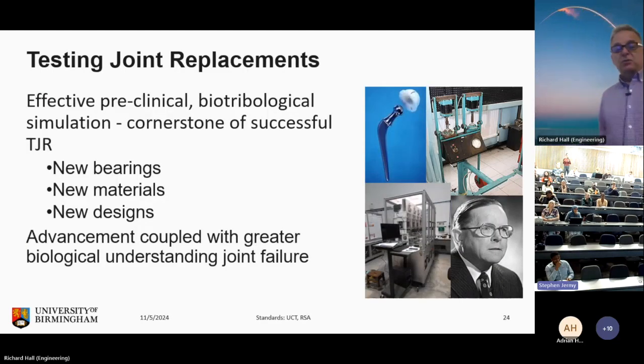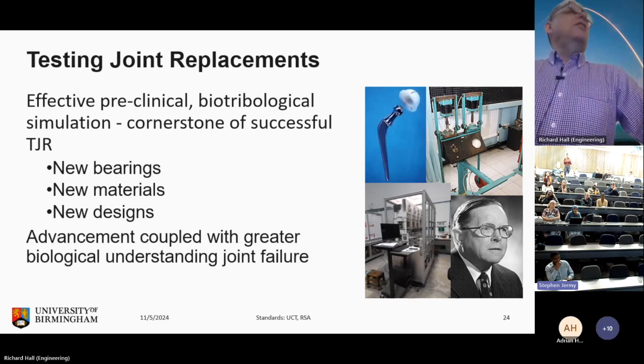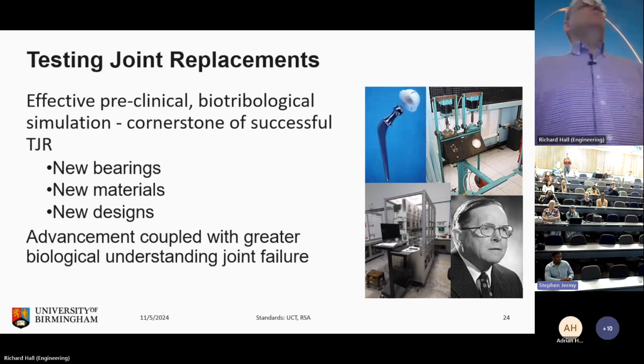So we test joint replacements. You come to our laboratory, we have big machines ranging anywhere from £250,000 to £1.5 million, £2 million, depending on the sophistication, the size, and the level of control that these machines exhibit. They can weigh anything from a few pounds to several tons, which has caused Birmingham a bit of an issue when trying to put these heavy machines in the first floor of a building. And now they're going to be put through the roof. They're going to take off the roof and lower them in with a huge crane, but I won't be there to see it.